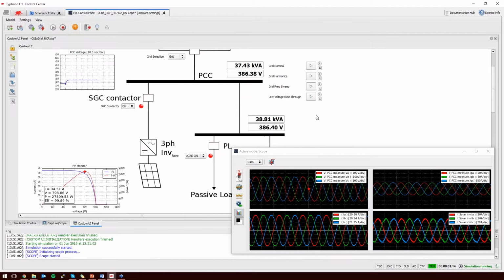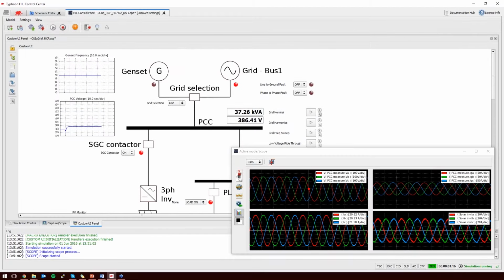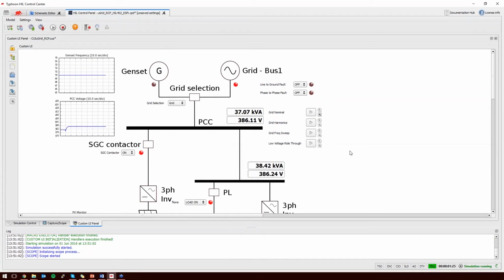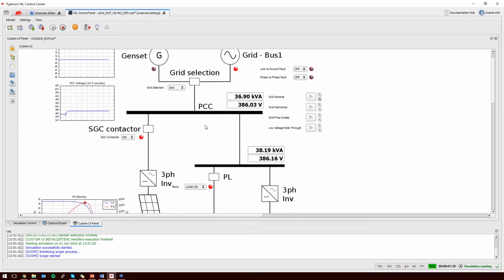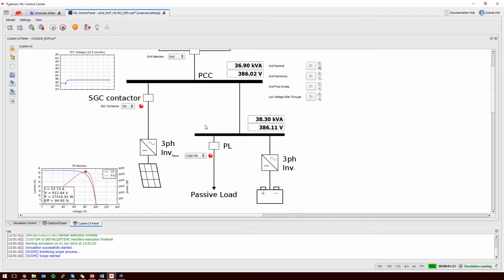One important thing here is how this all ties back together: you look at your response to these various faults inside the real-time simulation. You can see if your grid-tie inverter is acting the way you want it to, and if it isn't, you can bring those scenarios back to PSIM and fine-tune your control algorithm there, regenerate the code, flash back your DSP, and try again quickly.